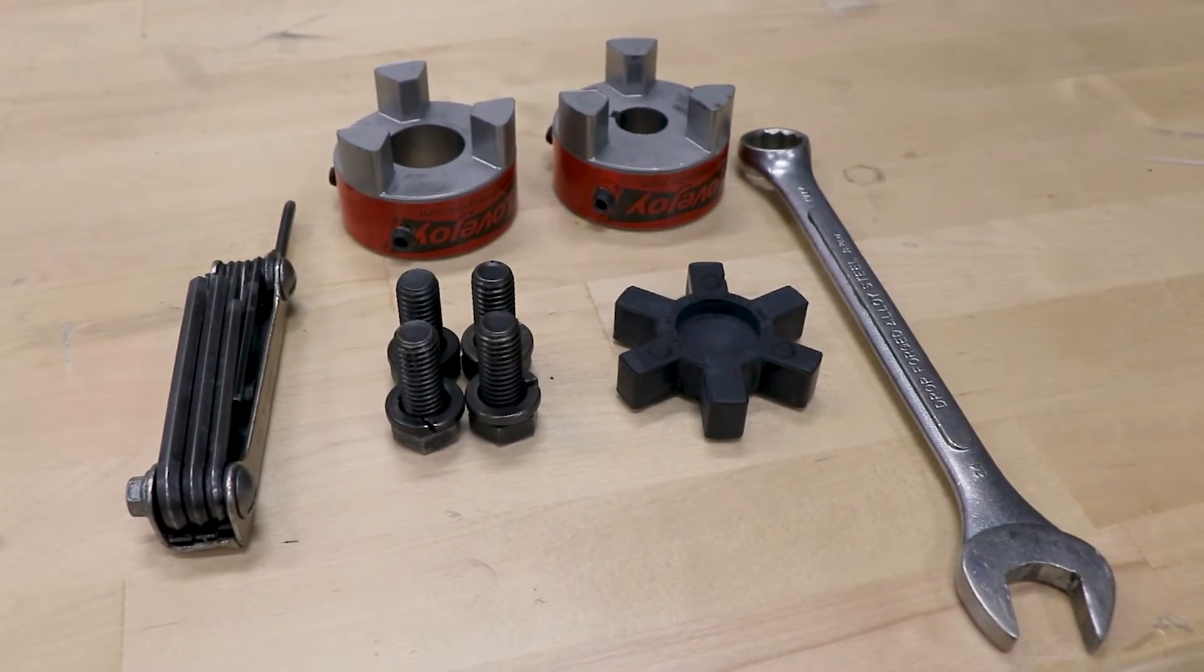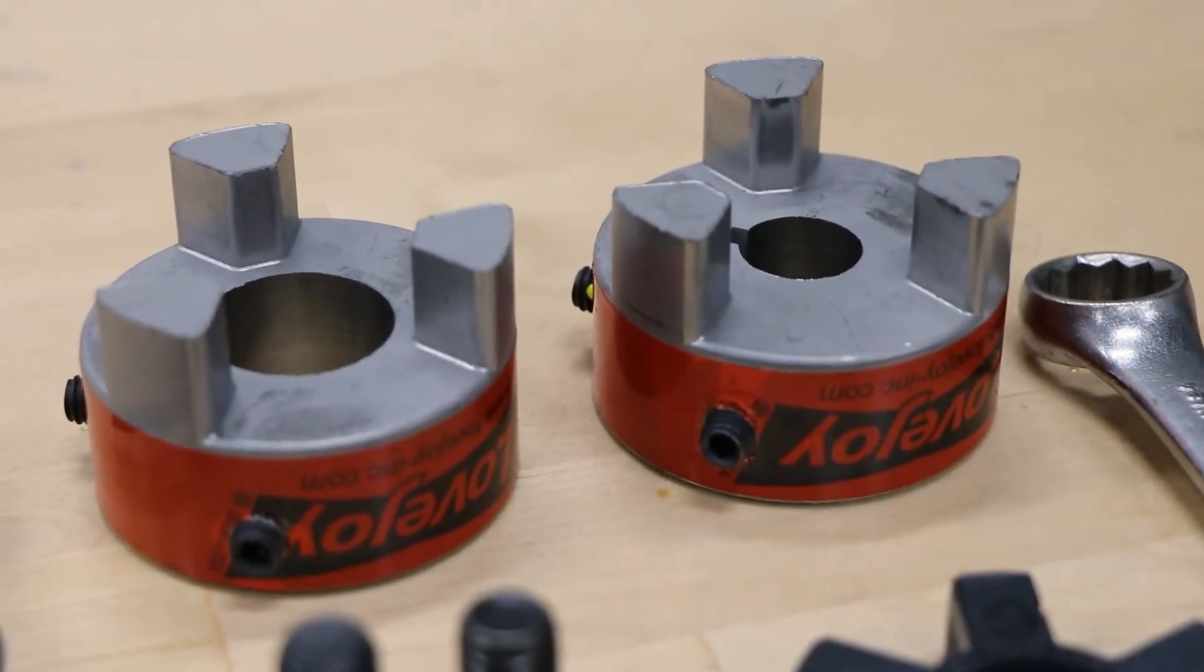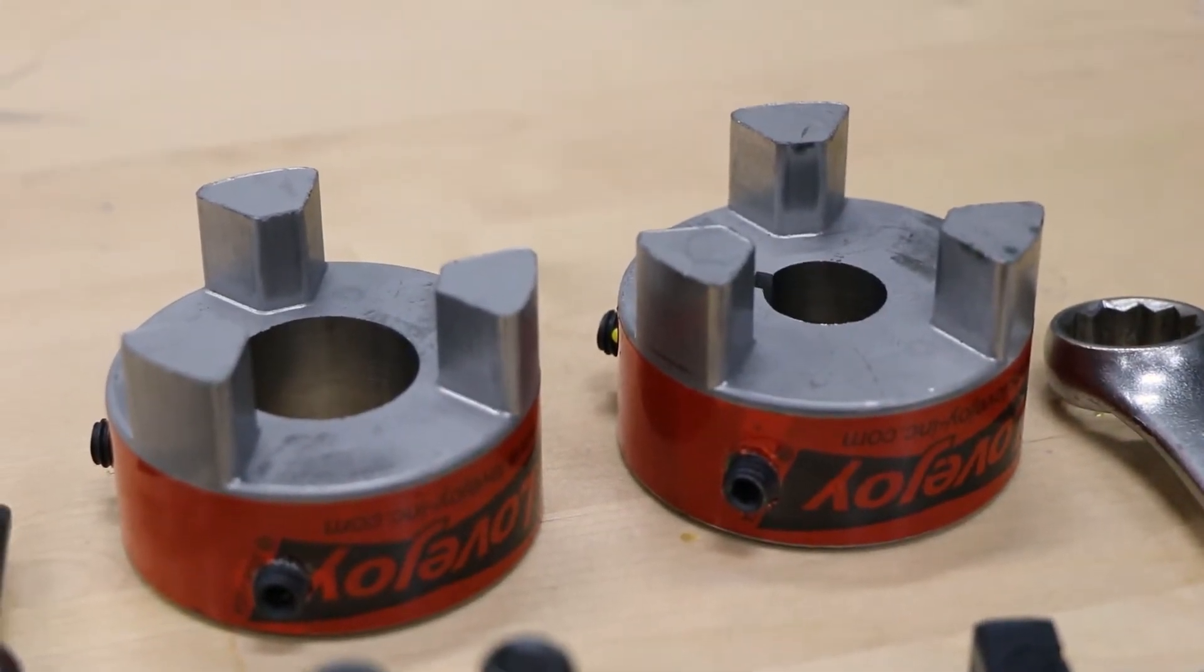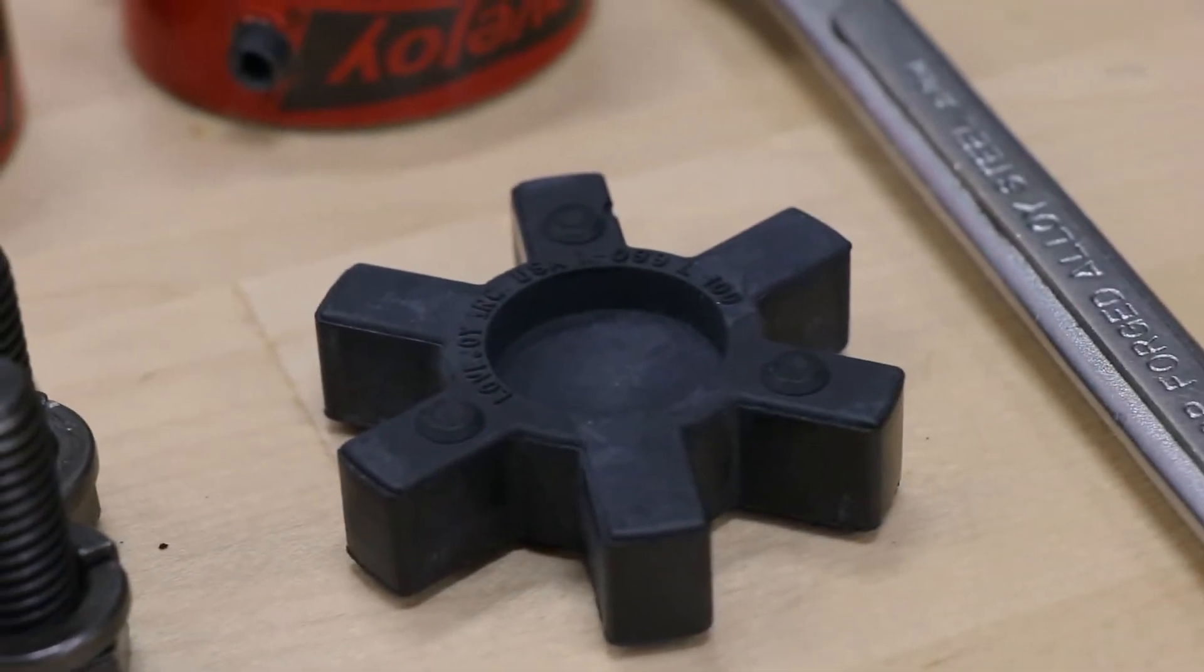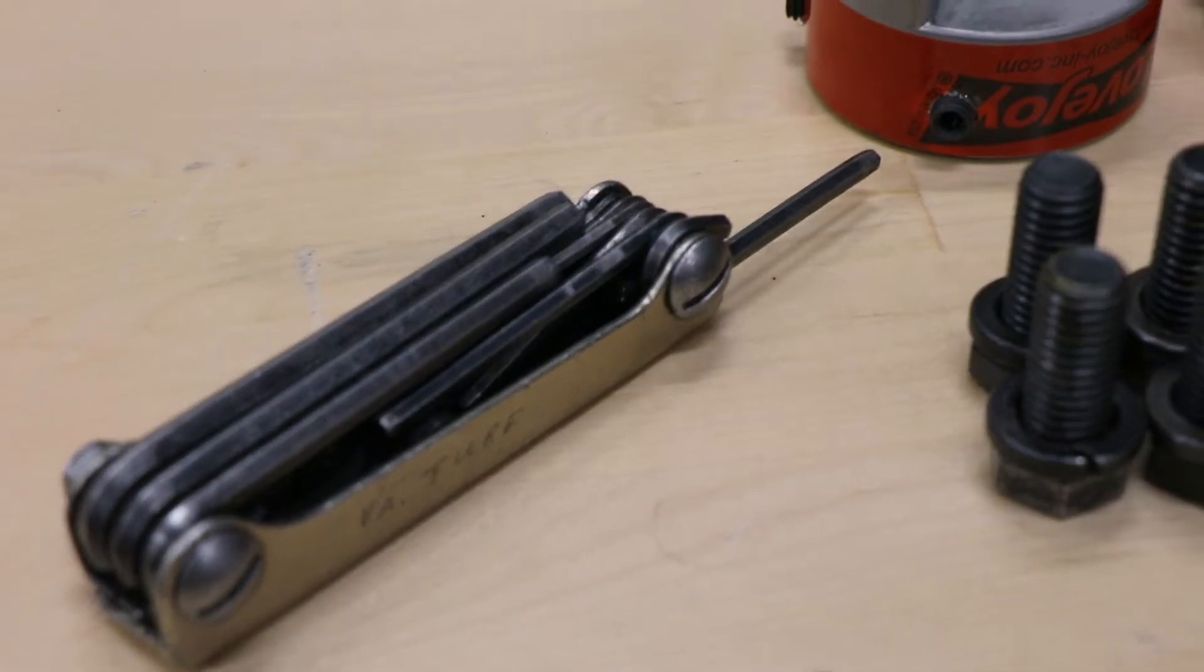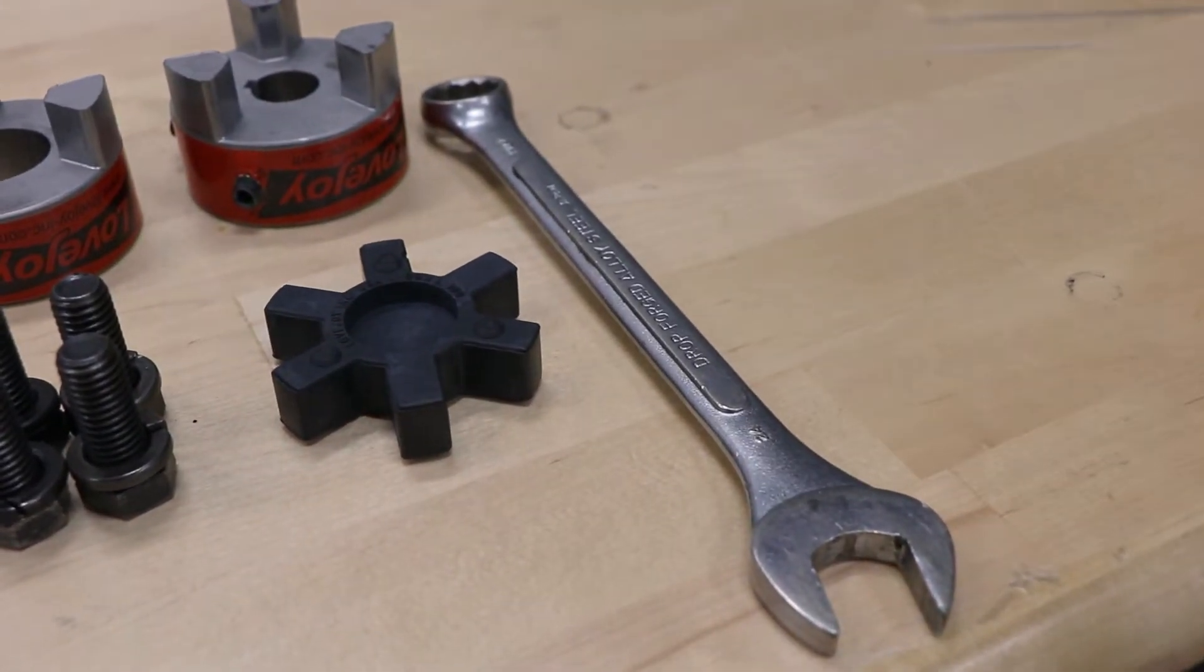For the first step, we want to make sure we have all the components for the install. Here we have the coupling halves—one side for the motor, one side for the reducer. We also have the bolts for the motor connection, as well as the coupling spider. Make sure you have all that with your Allen wrench to set the coupling spacing and the appropriate wrench.